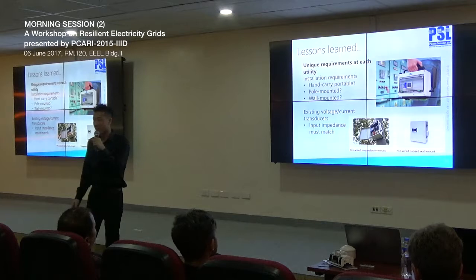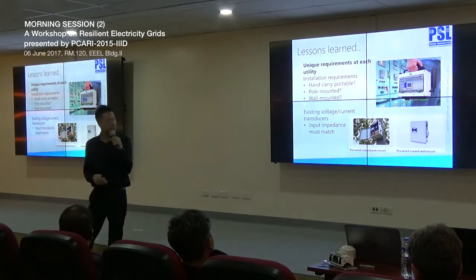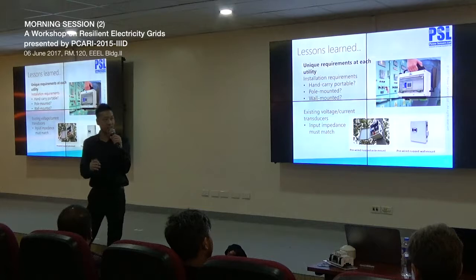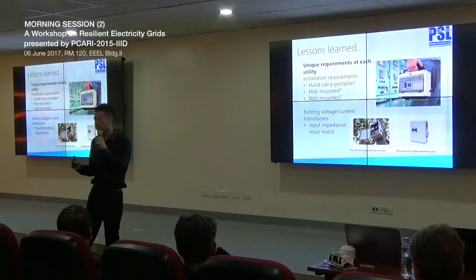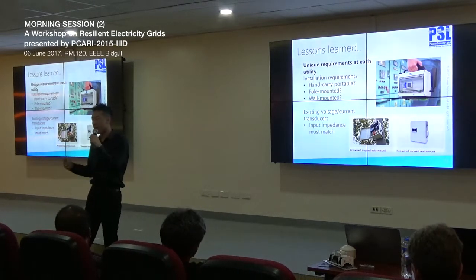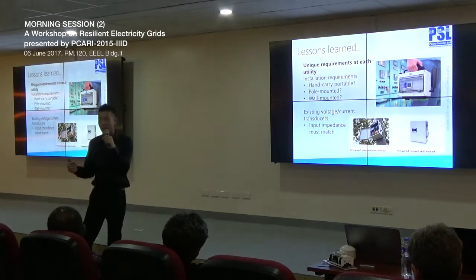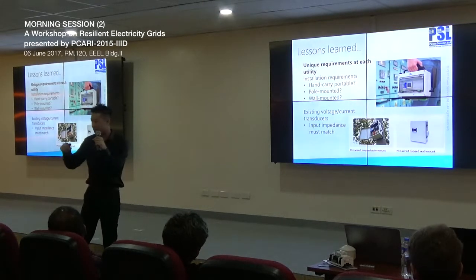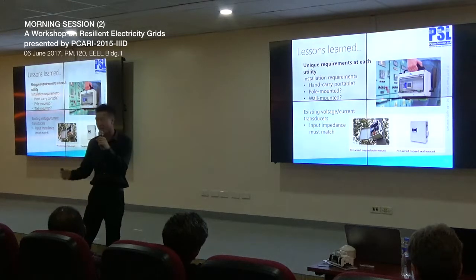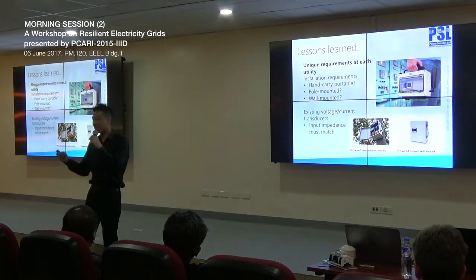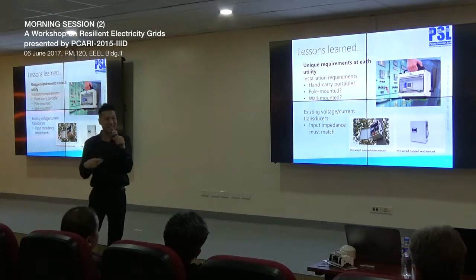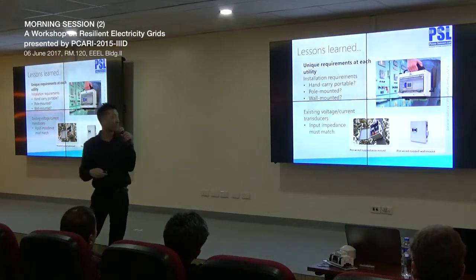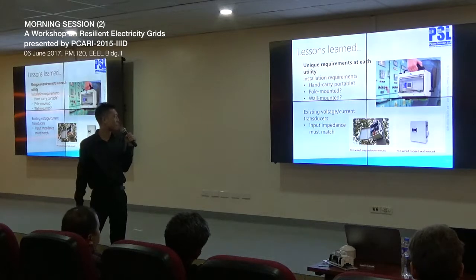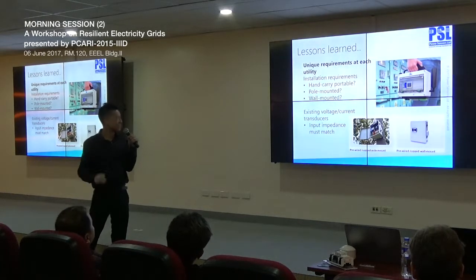Based on my experiences as a project manager working with many different utilities, I've noticed each utility has their own requirements. One wanted all the PMUs mounted on the pole. Another wanted a portable box they could just drop at the tap mount. Another wanted to mount it in the wall. Another wanted to mount it in the panel in the switchgear. As the equipment supplier, we were obliged to accommodate all of these requests, and I'm glad to say we did eventually accommodate everyone, but it was a real struggle to do it.